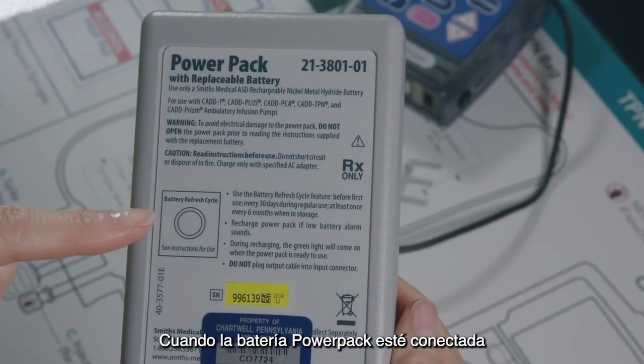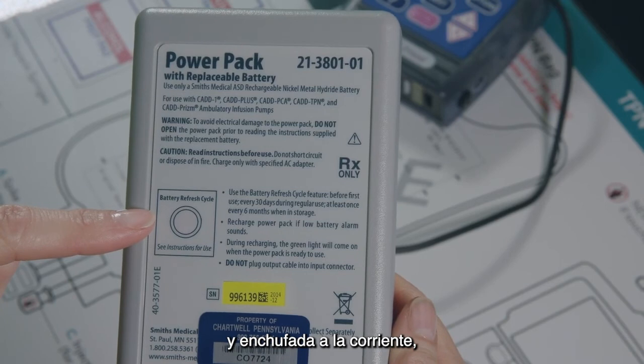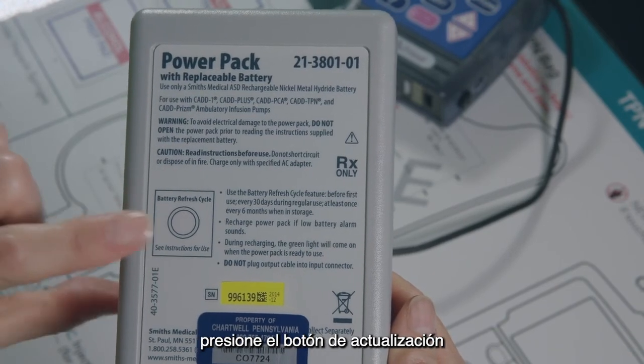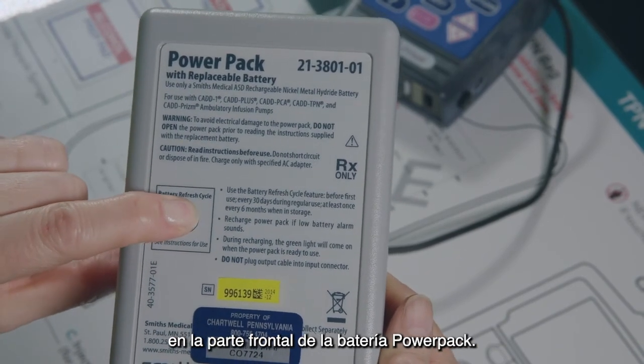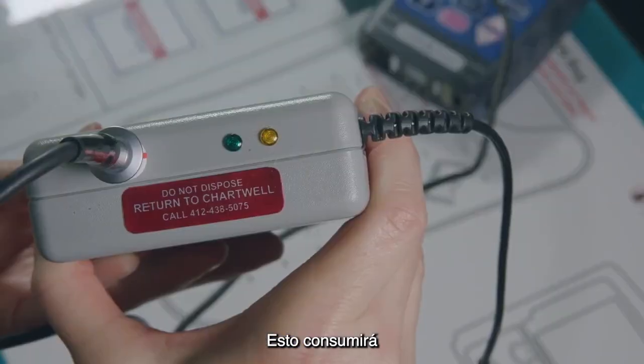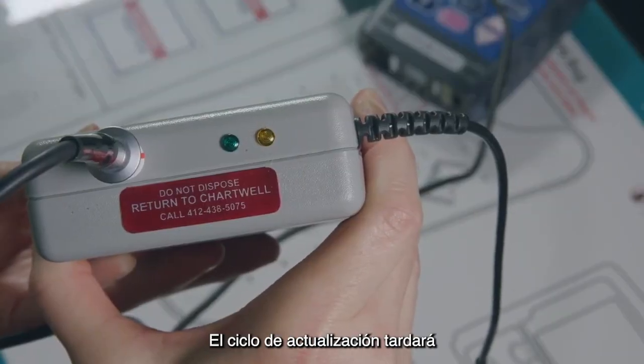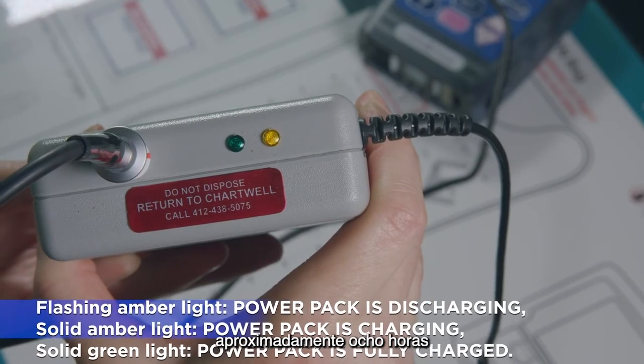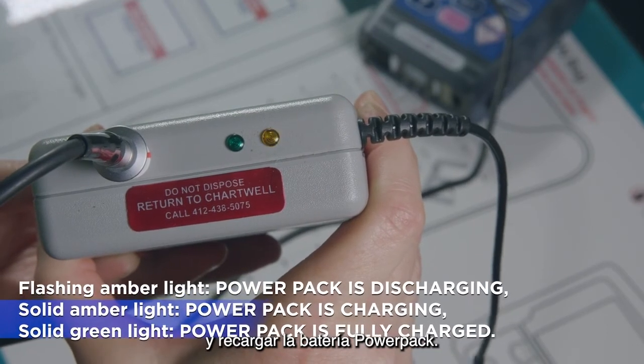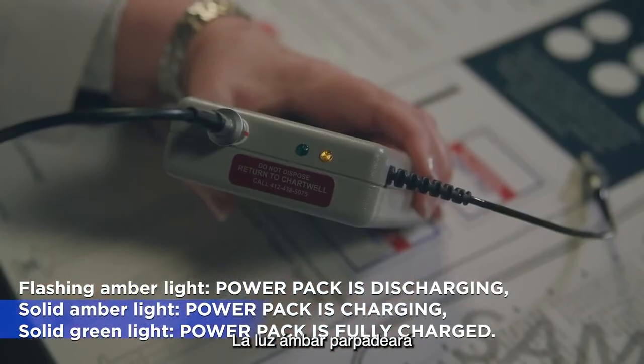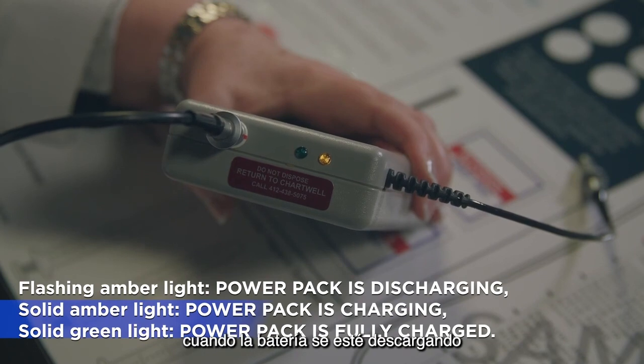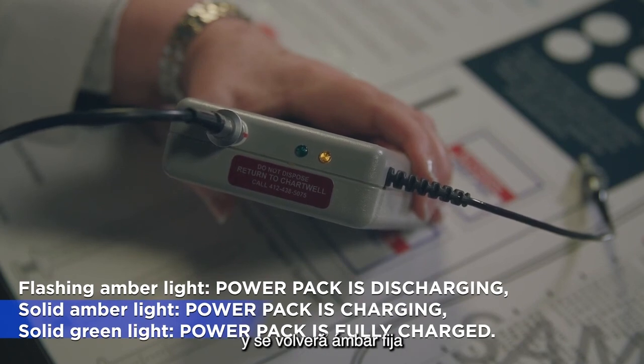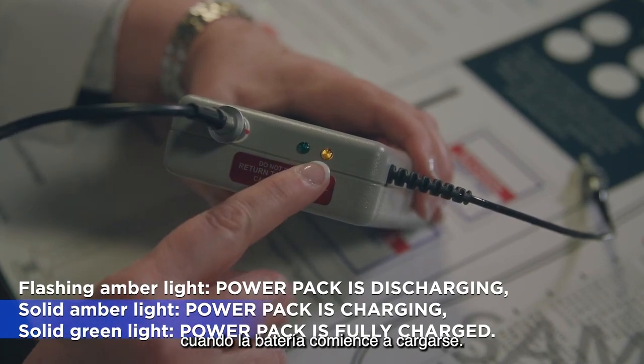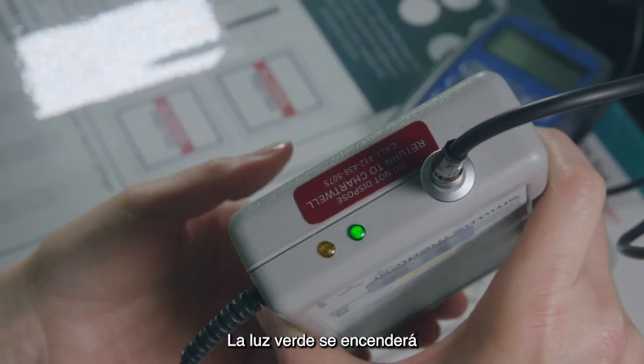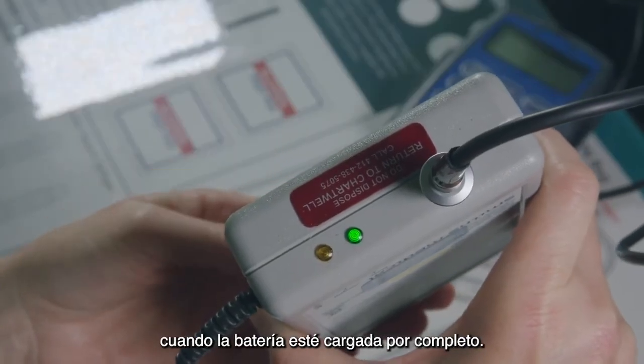Once the power pack is connected to the AC adapter and plugged into the wall, press the refresh button on the front of the power pack. This will drain all of the power out of the battery. The refresh cycle will take approximately 8 hours to completely discharge and recharge the power pack. The amber light will flash when the power pack is discharging and will turn solid amber once the power pack begins to charge. The green light will come on when the power pack is fully charged.